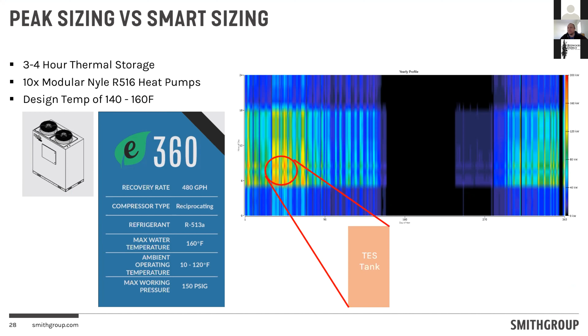In this case, we're looking at a new R513 machine that can make 160-degree water all the way down to 5 degrees or so. But we don't have to install two of them, because we're able to shave those peaks and understand the load profile of the building we're actually designing. That's important, because space is always an issue.